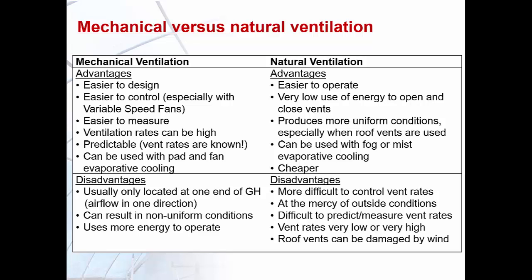Natural ventilation systems are easier to operate, use very low energy to open and close vents, and can achieve more uniform conditions in the greenhouse. They can be used with fog or misting systems for evaporative cooling and are cheaper. However, natural ventilation is more difficult to control to achieve certain ventilation rates because we are at the mercy of outside conditions. Ventilation rates are difficult to predict and measure, and roof vents can be damaged under high wind conditions.